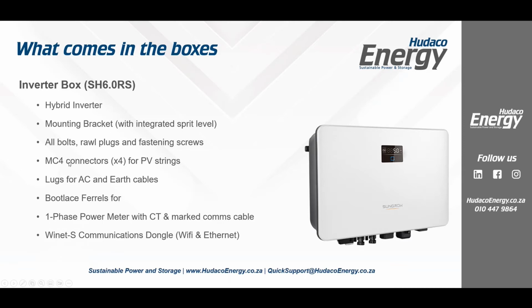In the box as well, you get MC4 connectors for your 4 strings. So you'll see down there, you've got MC4 points coming in. That's 2 strings, 30 amps on each one, or 2 MPPTs, 30 amps per MPPT, so you could run multiple strings there if you wanted. You also get all of the lugs for your AC and earth cable, comes in the box. You don't even have to go and get others.